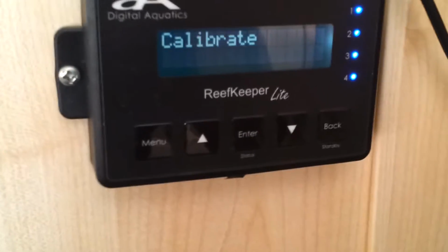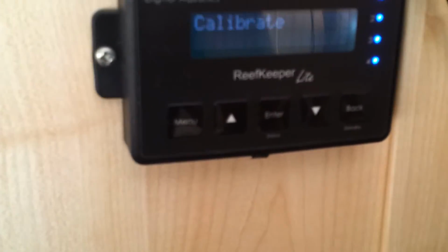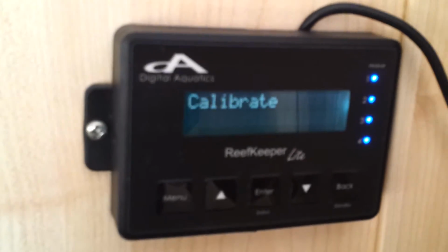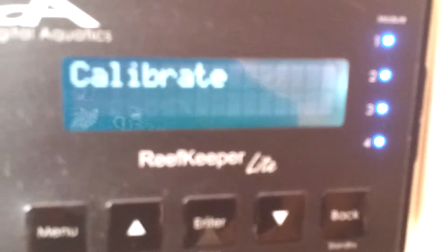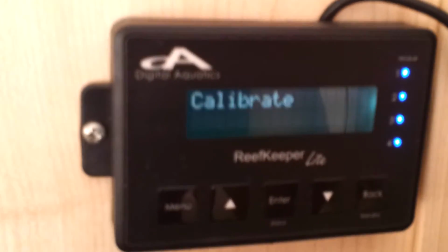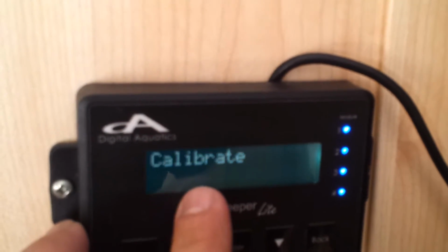You're gonna start seeing the numbers jump around. Wait about 3 minutes. The numbers actually come up pretty quick. It's not going to jump around like a pH Pro calibration. You're going to calibrate this pretty quickly. So like about 3 minutes, you're going to see the numbers be steady at a certain point. And then you're going to push enter. And then you're going to see 000. And then you're going to see the numbers at the end. So you want to change that to 053.